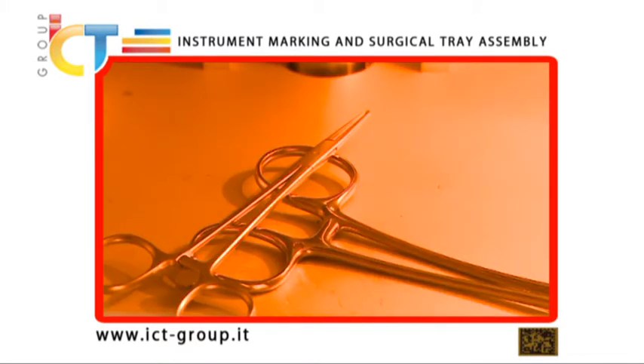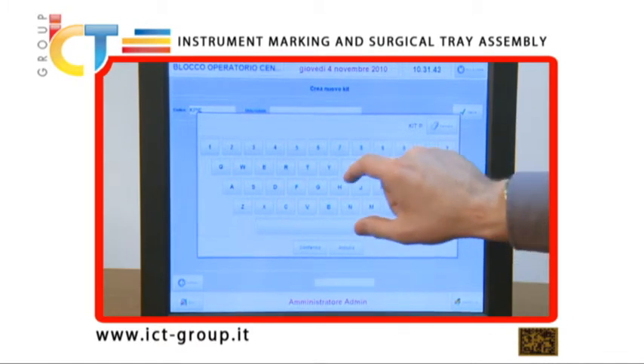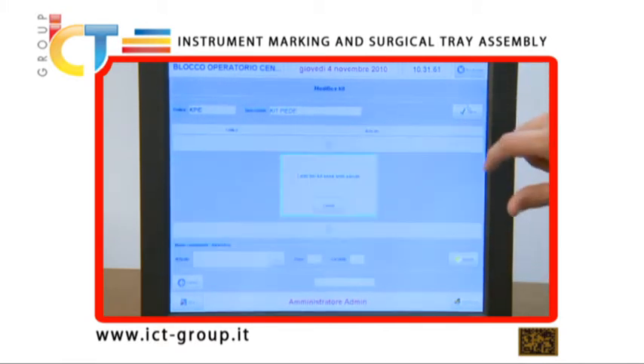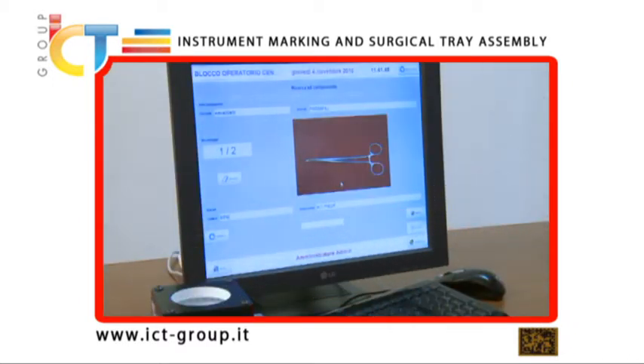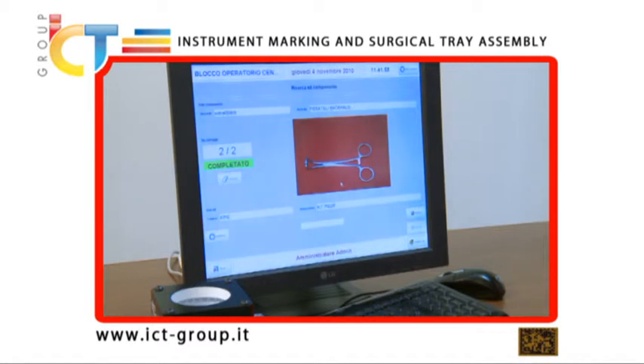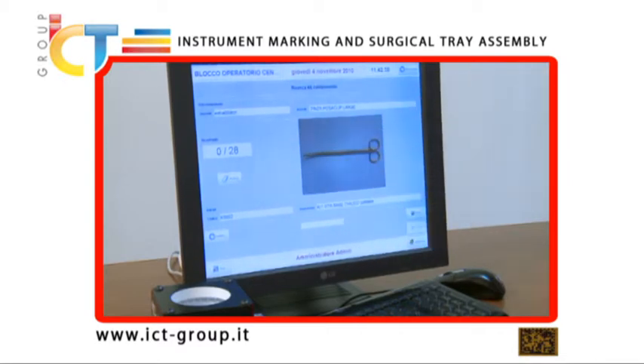This technology, when used in operating rooms and/or in sterilization facilities, will easily manage surgical tray codes in the system, the survey of all instruments and their arrangement in trays, and the assembly of individual surgical trays. In sterilization facilities, after instrument engraving and database generation, the system allows the operator to pack sterilized surgical trays. Reading the codes engraved on every instrument, the system gives the operator important feedback and information about the composition and the location of the tray of reference, including pictures of instruments if needed. This avoids any possible error and also allows non-skilled operators to assemble surgical trays.